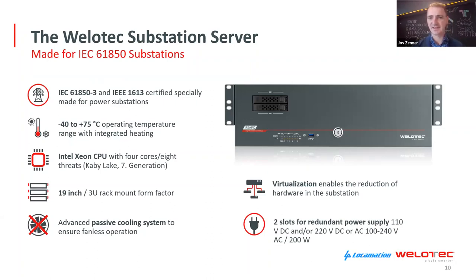First of all, it's a standardized x86 hardware platform, which is an Intel reference architecture, so it's very comparable to a standard server. But on the other hand, it meets the requirements of IEC 61850-3, which means EMC level and requirements for usage in power substations. It also meets the requirements of IEEE 1613, which includes vibrations, temperature, shock, and so on, so that it has the same environmental characteristics as traditional IEDs.